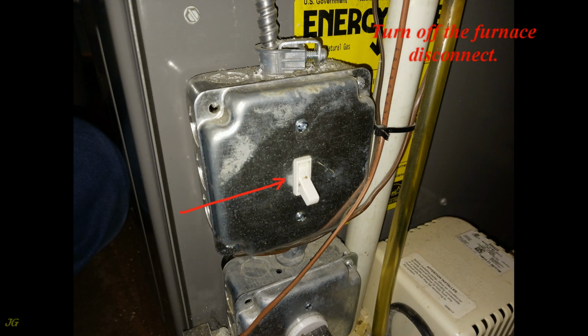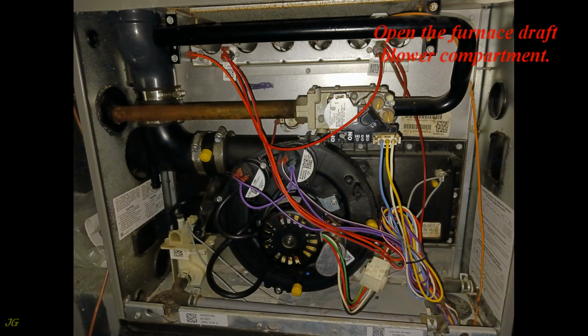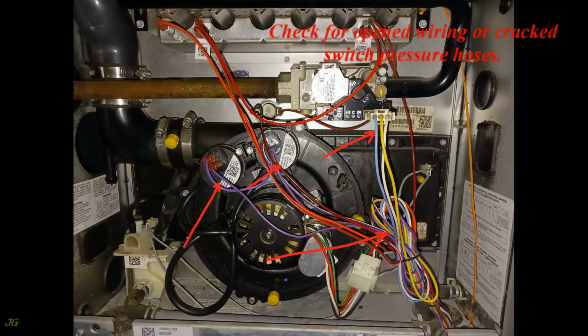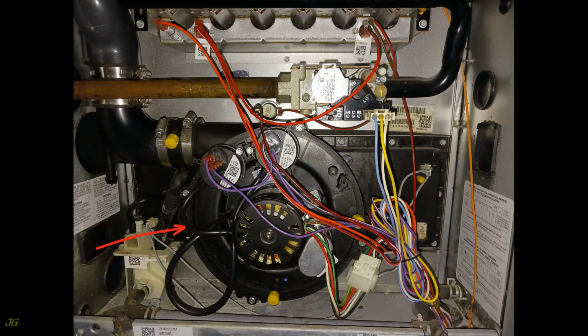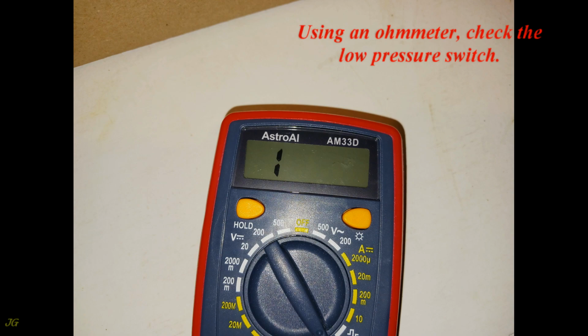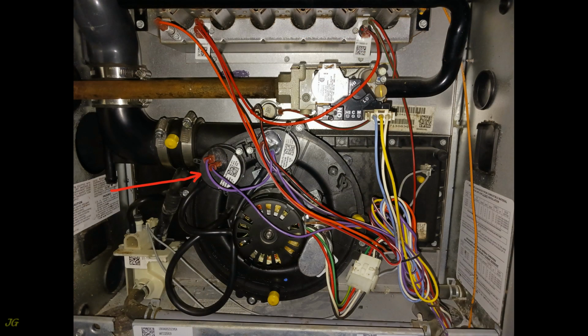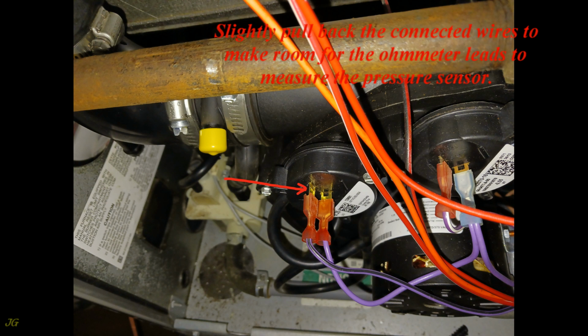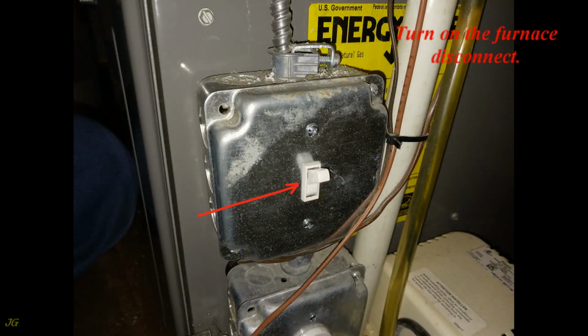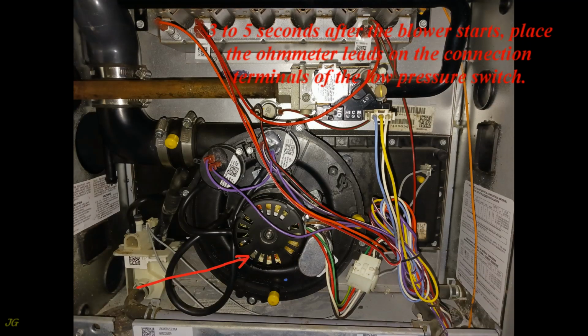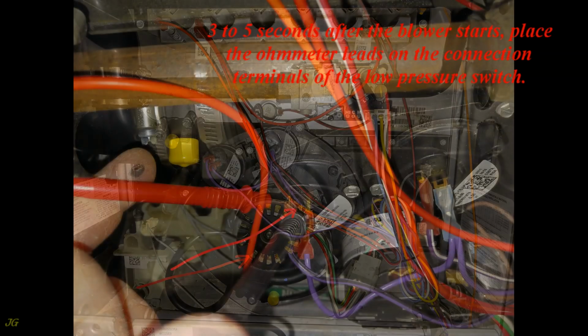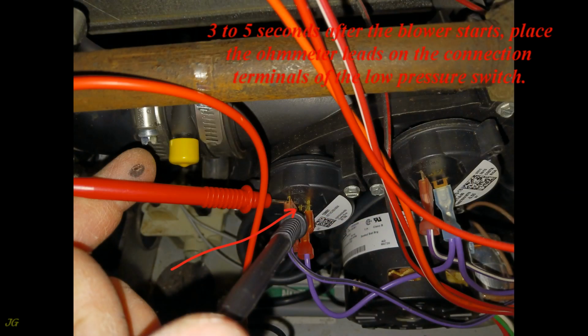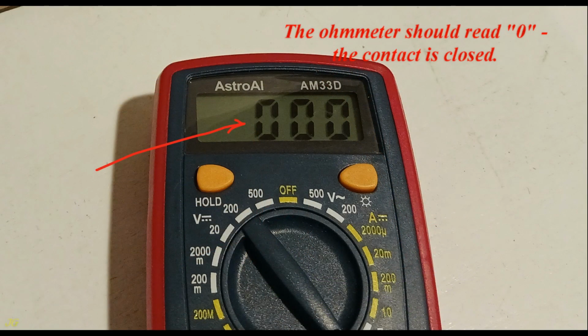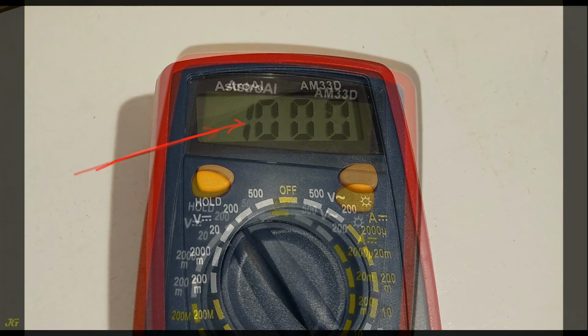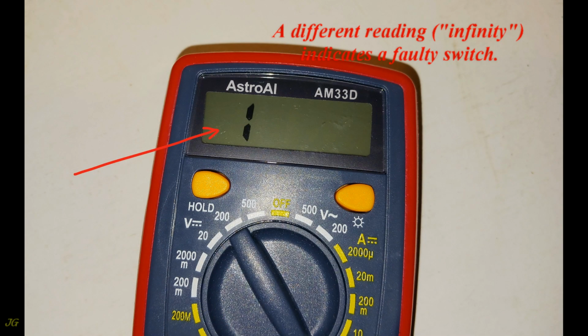Turn off the furnace disconnect. Open the furnace draft blower compartment. Check for opened wiring or cracked switch pressure hoses. Using an ohmmeter, check the low pressure switch. Slightly pull back the connected wires to make room for the ohmmeter leads to measure the pressure sensor. Turn on the furnace disconnect. 3 to 5 seconds after the blower starts, place the ohmmeter leads on the connection terminals of the low pressure switch. The ohmmeter should read 0, the contact is closed. A different reading, infinity, indicates a faulty switch.